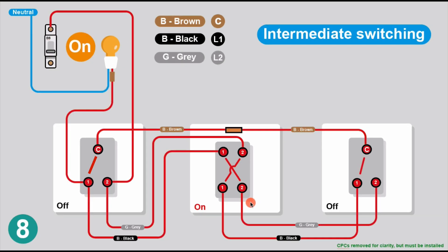This is the eighth and final combination of switching. With three switches, there are eight different positions the light can be in, so you want to check through them all to make sure your lighting is working correctly. The light is going to be on in this configuration. Following the power: it can't get to the common, so it goes through two on the grey, through the intermediate where it's crossed over, through the common, back to the first switch, and onto the light. The light is on. That covers all eight positions for intermediate switching.